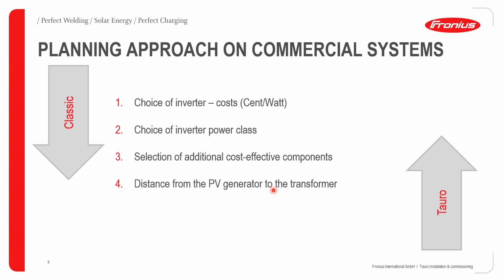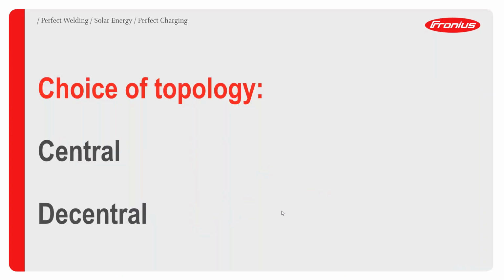Is it a rooftop system? Is it a field system? And therefore, what is the configuration around DC and AC cabling and how these are connected to the inverter? So going further into that, we can now discuss the choice of topology. And when you're talking about topology, we are talking about how the inverter is connected to your PV system. So we have two ways that we can use the Fronius Tauro, and one is a centralized topology, and the other one is a decentralized topology.